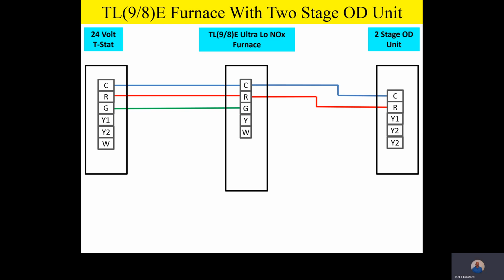Okay, at this time, let's go ahead and talk about a real simplified block diagram to hook up a 2-stage cool, 1-stage heat, 24-volt thermostat with our TL9/8E ultra low NOx furnace and a 2-stage outdoor unit. Now, it should be noted that the first stage of cooling on this 2-stage outdoor unit will be 67% capacity.